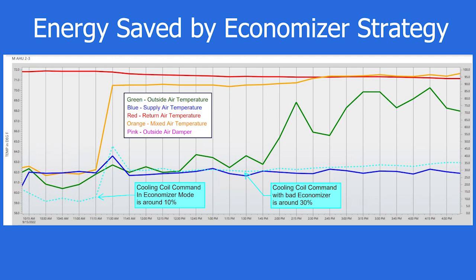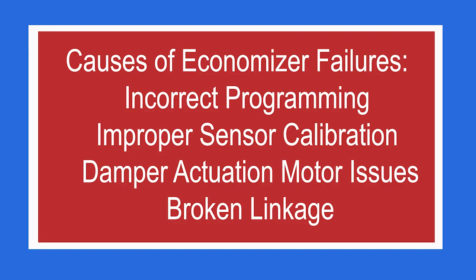You can see here how when we were in economizer mode, the cooling coil command, that's this light blue line, is only around 10%, which is all the mechanical cooling required to keep the desired temperature. And it looks like once we stop economizing, we're using about 30% of that cooling coil energy. So this can translate to quite a bit of energy wasted. Potential issues that could cause economizers to not be working properly would be programming issues, sensor calibration, the damper actuator motor has failed, either failed with the damper open or closed, or the linkage is broken.